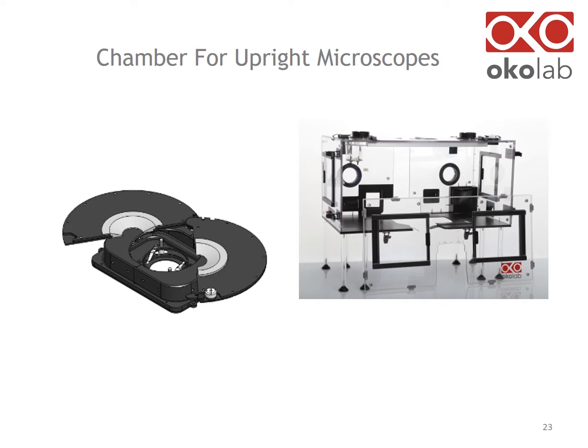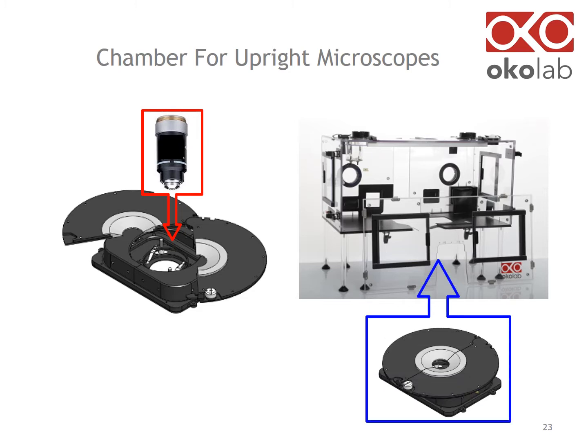If you are using an upright microscope, the chamber lid has an opening allowing the insertion of the objective. This opening is a route for evaporation of the media. For this reason, an upright microscope requires an active humidity system.